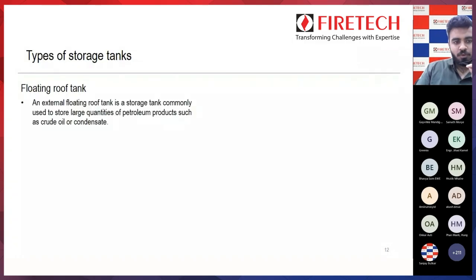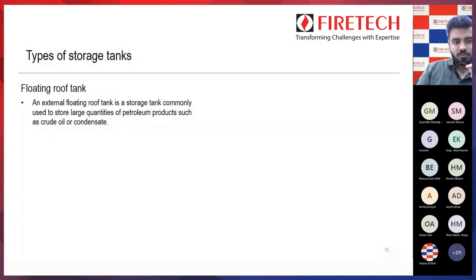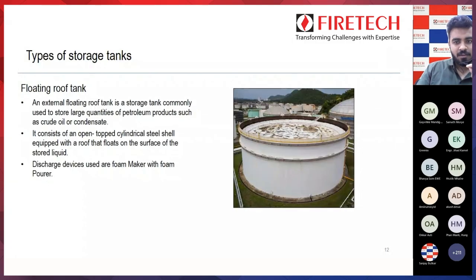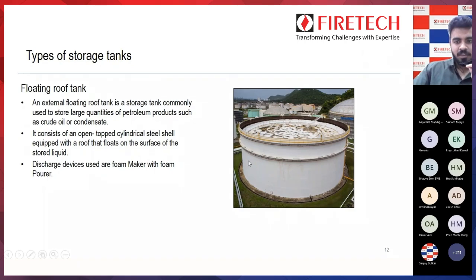Another type is the external floating roof tank. This has an open top and a floating roof which keeps on floating as the liquid inside the storage tank decreases. For this type, the discharge devices are foam maker with foam pourer.